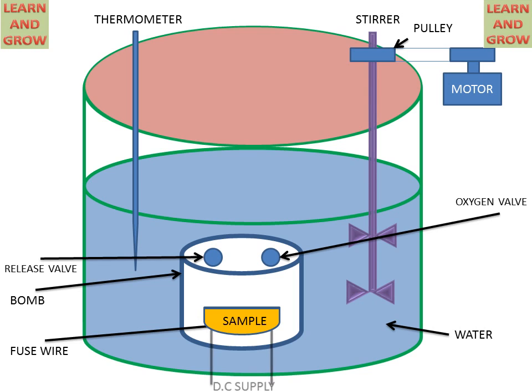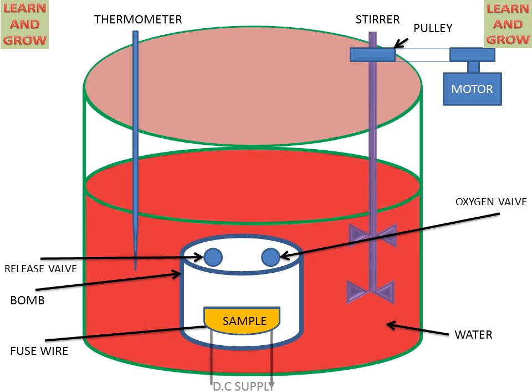Then, DC supply is given to this fuse wire and the sample starts burning or liberating heat. This oxygen valve is used for giving oxygen to the sample for complete burning process. Then, after burning of the sample, heat will liberate and it will increase the water temperature.